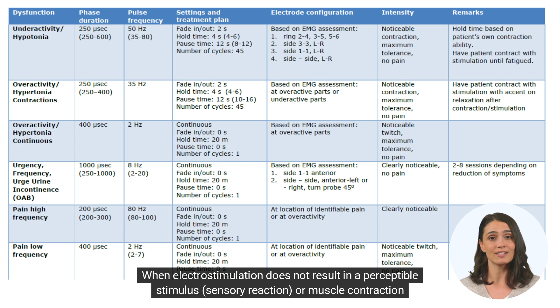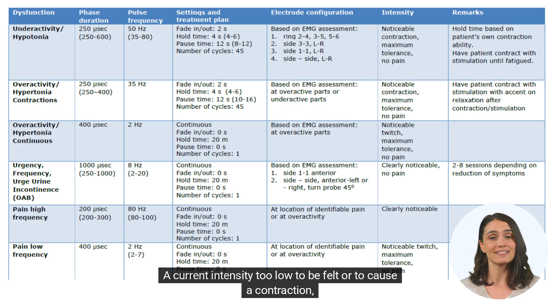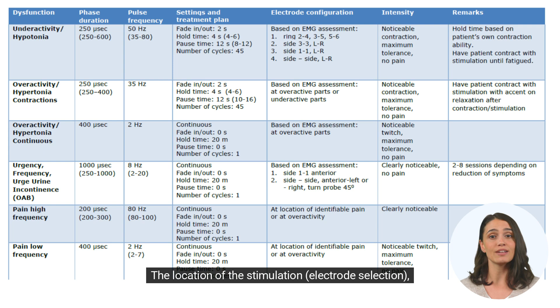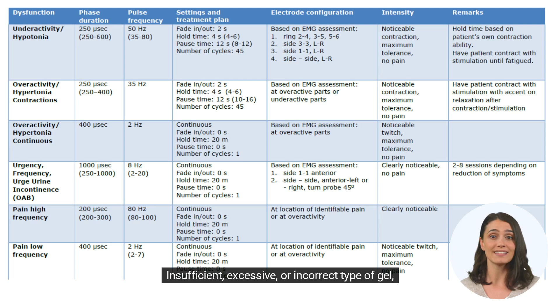When electrostimulation does not result in a perceptible stimulus, sensory reaction, or muscle contraction, motor reaction, this may be due to a current intensity too low to be felt or to cause a contraction, the location of the stimulation, electrode selection, non-optimal stimulation settings, insufficient, excessive, or incorrect type of gel, nerve damage.